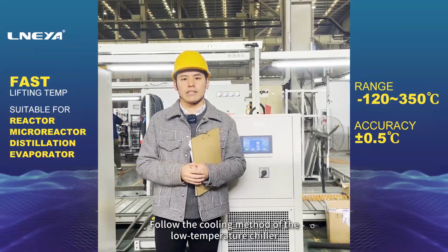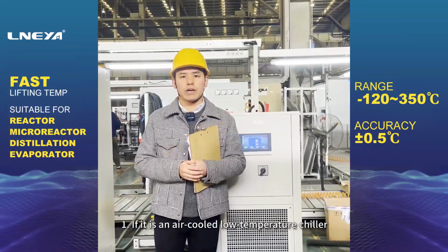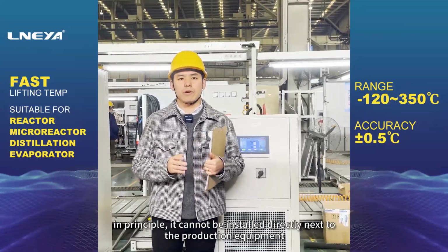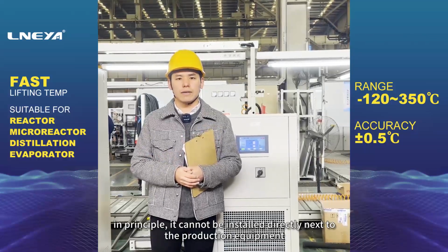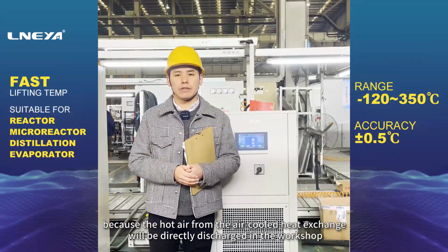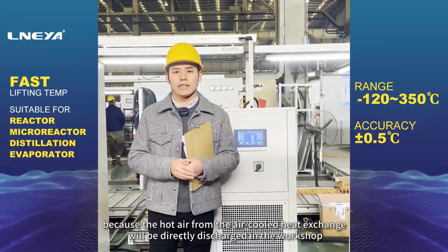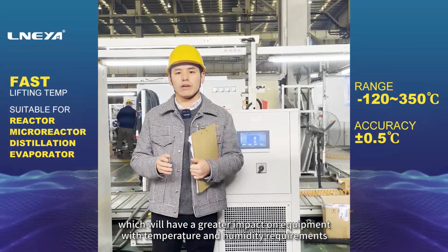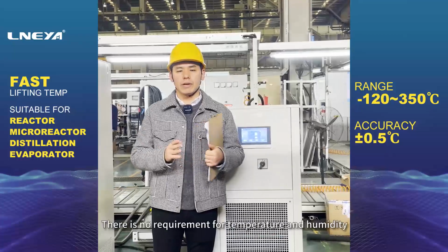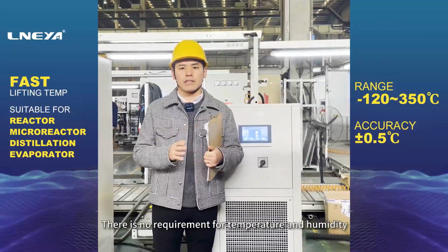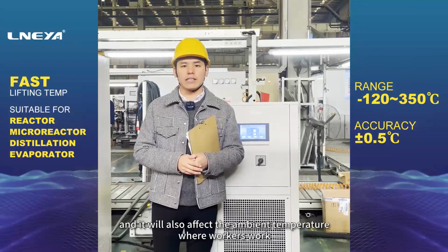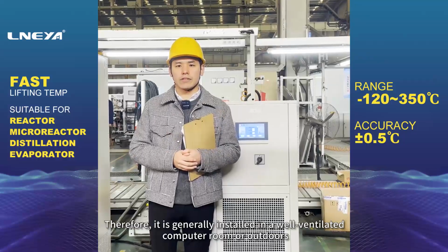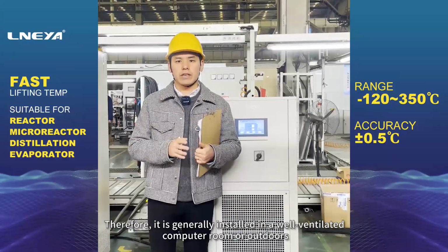Follow the cooling method of the low-temperature chiller. First, if it is an air-cooled low-temperature chiller, in principle, it cannot be installed directly next to the production equipment, because the hot air from the air-cooled heat exchange will be directly discharged in the workshop, which will have a greater impact on equipment with temperature and humidity requirements. Even where there is no requirement for temperature and humidity, it will also affect the ambient temperature while workers work. Therefore, it is generally installed in a well-ventilated computer room or outdoors.